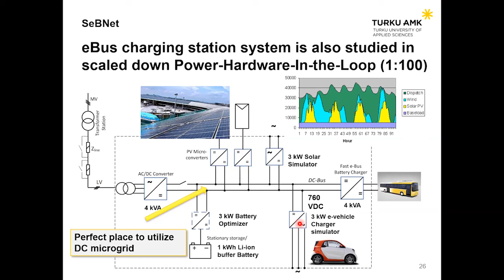I took exactly this picture on purpose. In the literature and in measurements, there is clear knowledge that when you multiply the number of converters, you have to take some measures about stability of converters. If all the chargers come from the same suppliers, the risk can be reduced, because they have their models and very good advanced knowledge of how to develop a converter and a controller. But if you start to mix different converters - for instance here I see PV production on the roof and its converter - you might get quite interesting surprises.